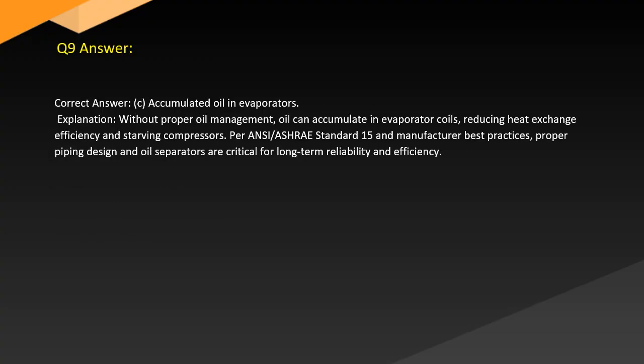Answer. Correct answer: C. Accumulated oil in evaporators. Explanation: without proper oil management, oil can accumulate in evaporator coils, reducing heat exchange efficiency and starving compressors. Per ANSI/ASHRAE Standard 15 and manufacturer best practices, proper piping design and oil separators are critical for long-term reliability and efficiency.